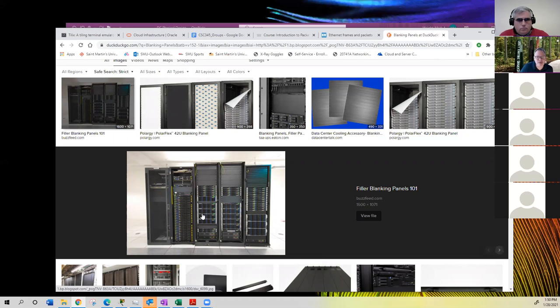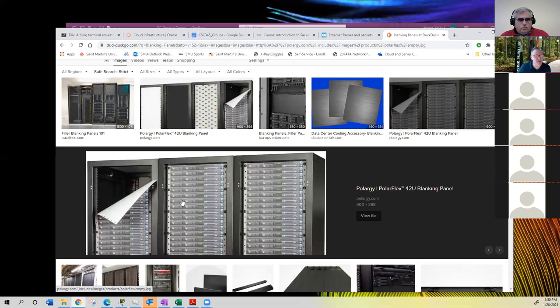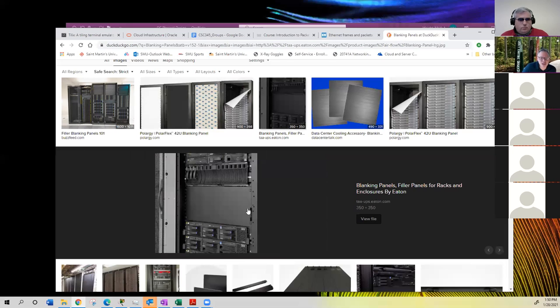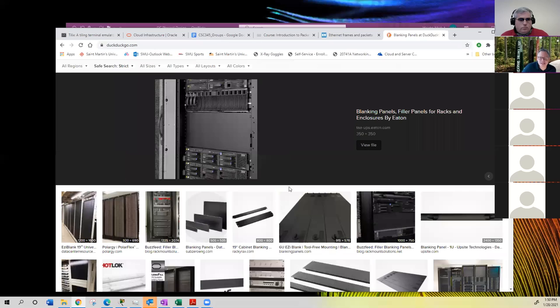So hot air can just come right through that rack and get mixed back in with the cold air in the front. One of the things you do is put in these blanking panels. This stuff here looks like servers but it's not, it's just paper, blocking hot air from coming back and mixing with the cold air. Typically though, it's an actual aluminum panel, painted like this middle square here, where we just bolted it in so your rack doesn't have this gap.